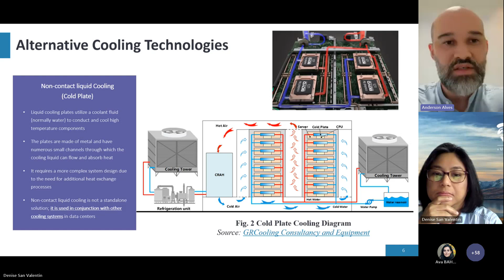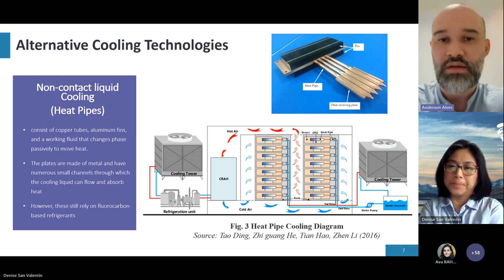Next slide, please. So the second technology would also be a non-contact liquid cooling technology, but instead of cooling plates, you use heat pipes. The principle is the same. These heat pipes have a different design. They would be in contact with the CPU and the GPU in the racks, but the liquid doesn't enter into direct contact with the IT equipment. The same as before, you can achieve energy efficiency in comparison to the baseline technology, but you still need a refrigeration unit to take care of the remaining heat load that stays in the data center. Next slide, please.